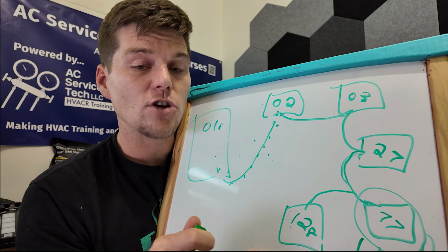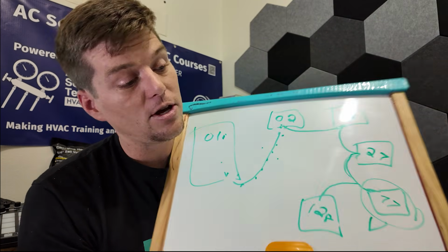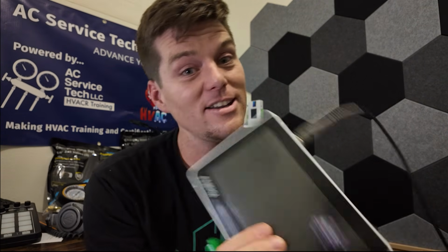And the process for that is always trying to get the outdoor unit to communicate to the very first indoor unit from the get-go. If you can prove communication, then you know that you're not troubleshooting an A1P board that will never communicate. There's nothing worse than trying to get a board to do something that you can't actually visually see without an oscilloscope: the data points that are being sent to the indoor unit and received back at the outdoor unit.